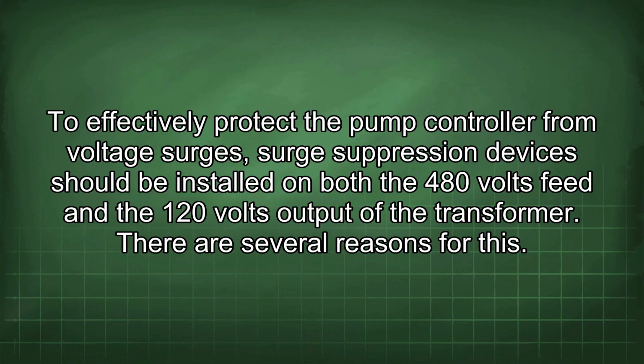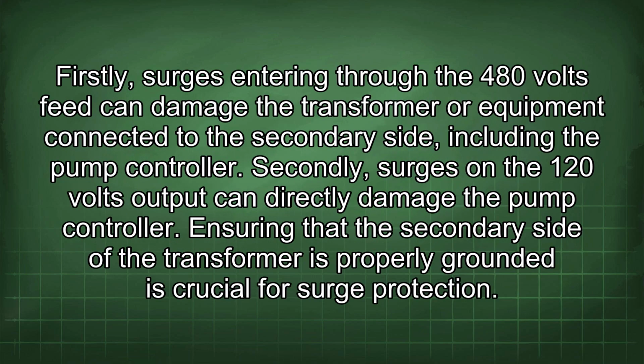To effectively protect the pump controller from voltage surges, surge suppression devices should be installed on both the 480 volts feed and the 120 volts output of the transformer. There are several reasons for this. Firstly, surges entering through the 480 volts feed can damage the transformer or equipment connected to the secondary side, including the pump controller. Secondly, surges on the 120 volts output can directly damage the pump controller.